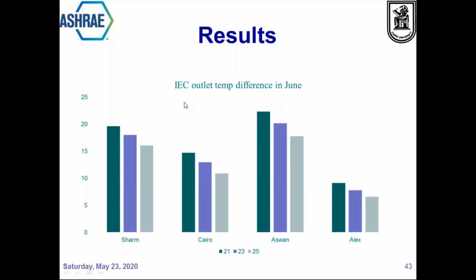So in Sharm el-Sheikh, when using indirect evaporative cooling, we can gain 20 degrees centigrade difference if we use water at 21 degree spray. While in Alex, this difference is less, naturally, because the air here is more humid. So its capacity to carry more water is less. While in Aswan, which is a little bit dry, with using indirect evaporative cooling, you have a temperature difference of 22 degrees centigrade. That's the difference between the primary air inlet and the primary air outlet.